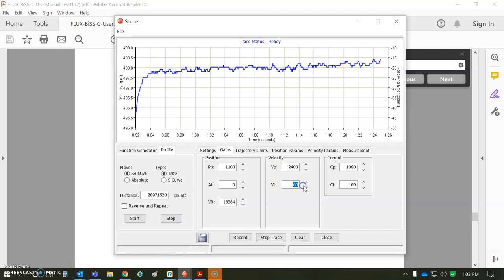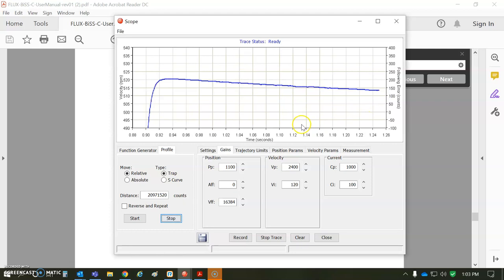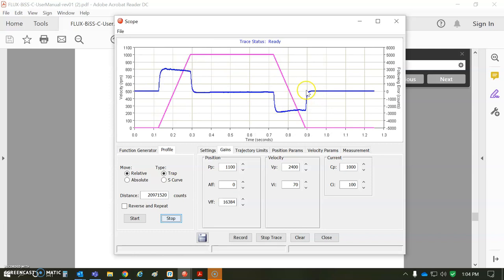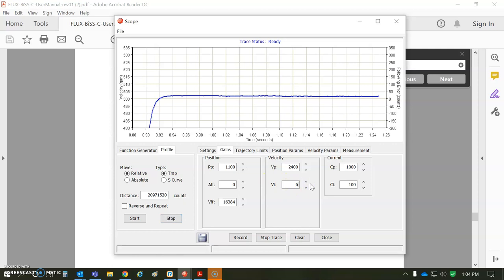Maybe do a little bit more integral here. You might get some overshoot on that though. Yeah, there's a little too much integral on that one, so it depends on your inertia and how close to the tracking window you're trying to get. We are within—let's just go back to a lower value. This system seems to be pretty well grounded. There's not a lot of excessive noise on the feedback device. Let's go back to the 60 again. That looked pretty good.